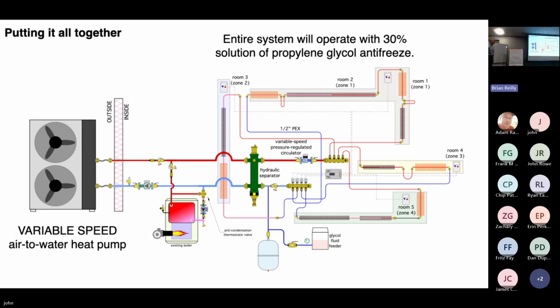I'd be extremely surprised to find an existing system with an anti-condensation valve, but if you're going to retrofit the heat pump and potentially run that system at reduced water temperatures to benefit the performance of the heat pump, you really need that anti-condensation valve. Particularly on new sidewall vented boilers? No, if it's a modulating condensing boiler, absolutely not. That'd be the worst thing you could do, actually. You want it to condense. But again, in many of those heat pump retrofit projects, you're probably going to find cast iron boilers with oil burners.